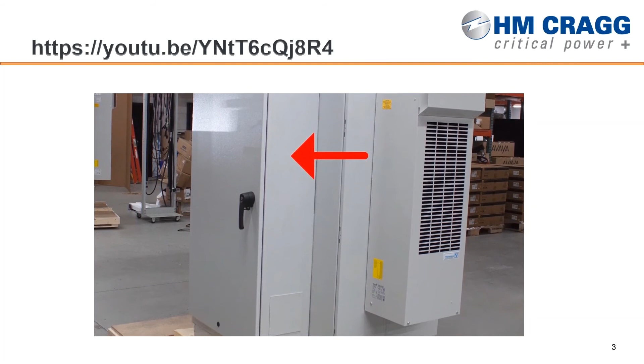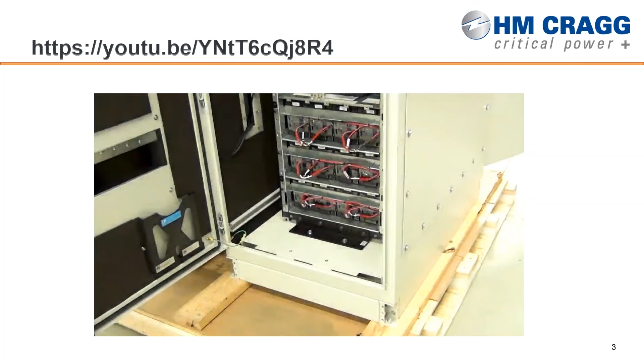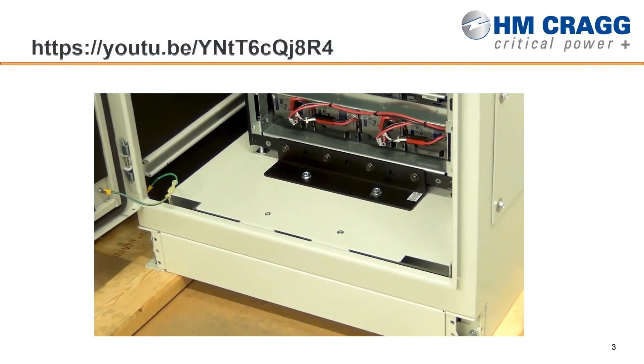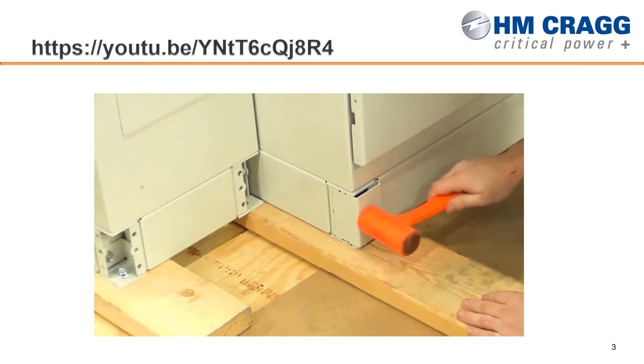We've got 2 discrete enclosure designs here, one for the main UPS and one for the bypass enclosure. They can be separated on site, so this is a pick and place type scenario. If the UPS were to fail, we could put the system in bypass, lift up the main UPS enclosure, and replace it with a new UPS system.